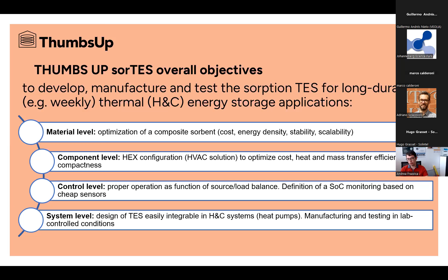Here are some of the targets we have in the project. I will focus mostly on the energy storage density. Generally, energy storage density reduces from material level down to system level because of other components like vessels and heat exchangers that reduce the overall density. Our aim is to reach up to 120 kilowatt-hours per cubic meter when the system is integrated inside the building, considering also the heat losses faced during weekly operation. We also target reducing the cost of the composite sorbent material down to a maximum of 5 euros per kilogram, and reaching a capital cost lower than 200 euros per kilowatt-hour of storage capacity.